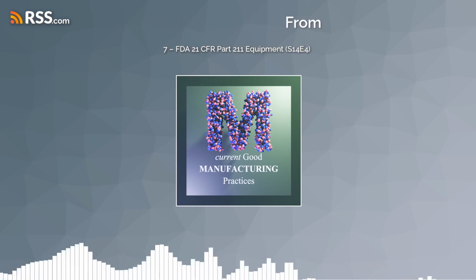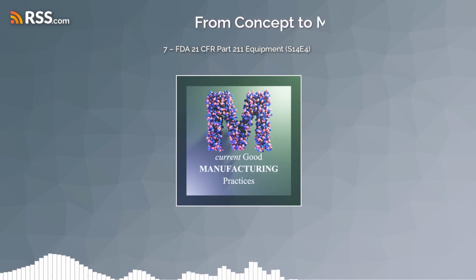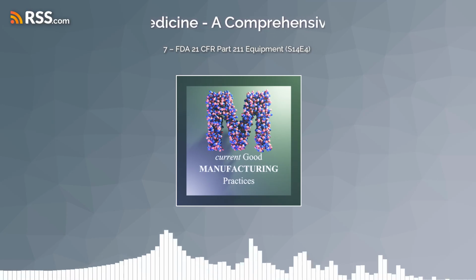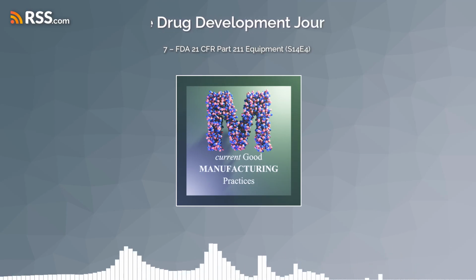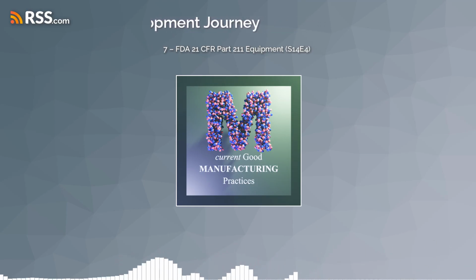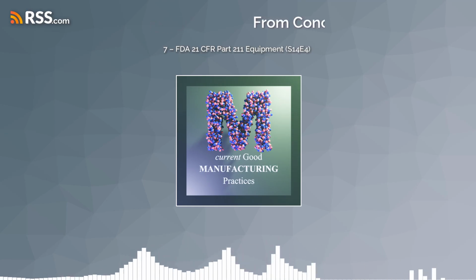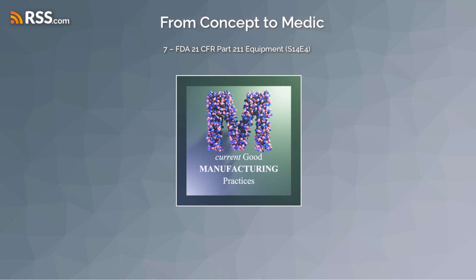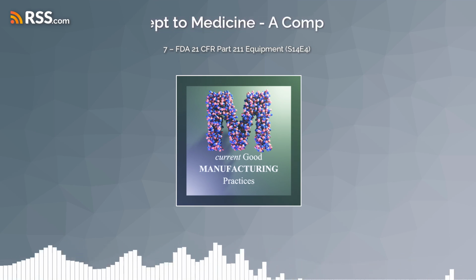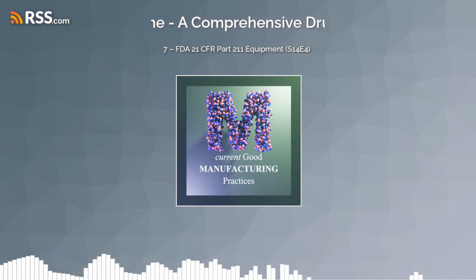So you're looking for any potential flaws in the design that could affect the equipment's performance or maybe increase the risk of contamination. Exactly. You might look at the materials used to build the equipment to make sure they're compatible with the products being manufactured, make sure they won't leach any harmful substances. You'd also look at the equipment's controls and safety features to make sure they're appropriate for the way it's going to be used. Okay, so DQ is all about making sure the equipment is designed for safety and effectiveness right from the start. What about installation qualification, or IQ?